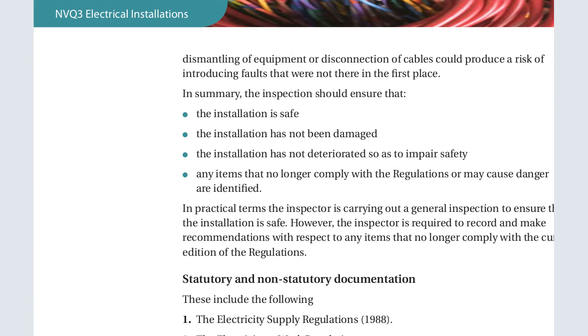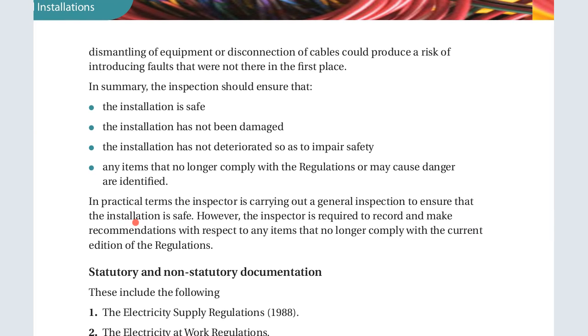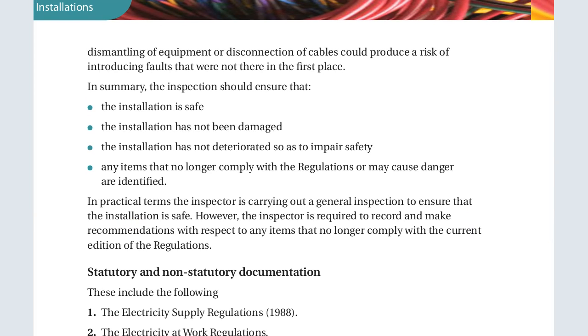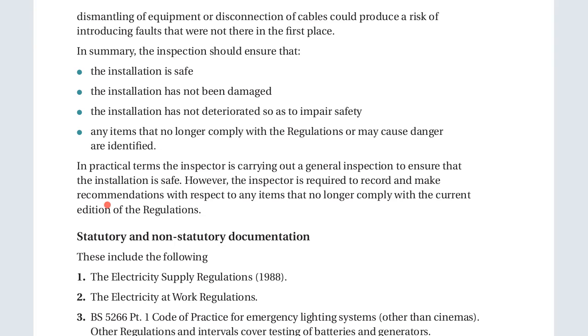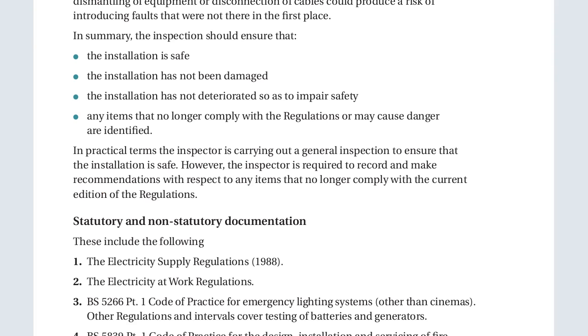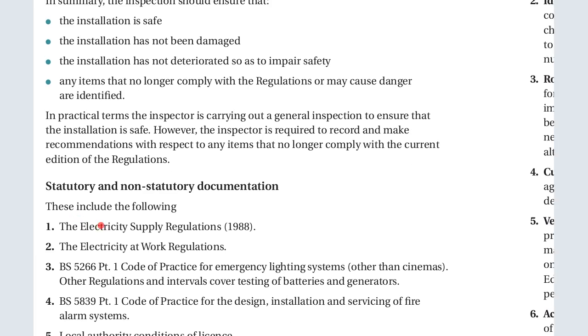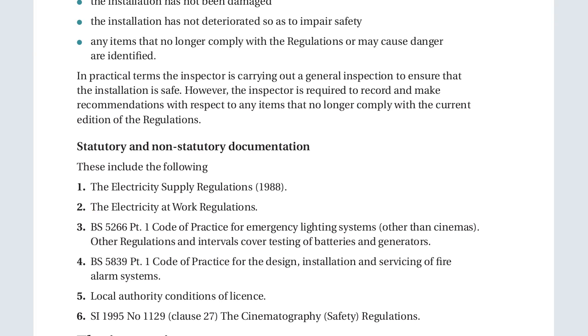It is considered that unnecessary dismantling of equipment or disconnection of cables could produce a risk of introducing faults. So in summary, inspection should ensure, number one, that the installation is safe. Another is that the installation has not been damaged. Another is that the installation has not deteriorated so as to impair safety. And another is that any items that no longer comply with the regulations or may cause danger are identified. So in practical terms, the inspector is carrying out a general inspection to ensure that the installation is safe. However, the inspector is required to record and make recommendations with respect to any items that no longer comply with the current editions.